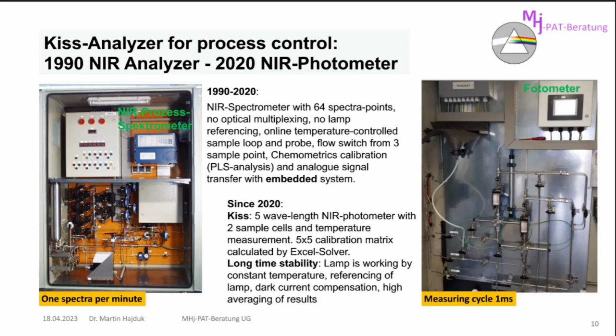So 3 years ago, we decided to switch to an NIR photometer with 5 channels, and we are using 2 sample cells. We reduced the situation to 2 photometers, so 2 cabinets with 2 photometers and only 2 sample points. And for calculating the concentration, we don't use PLS and chemometric calibration anymore. We use Excel with a solver and a 5 by 5 calibration matrix. We can also calculate the influence of the temperature because we measure it. It's not stabilized to a constant temperature. We measure the temperature and can include it in the calibration matrix.